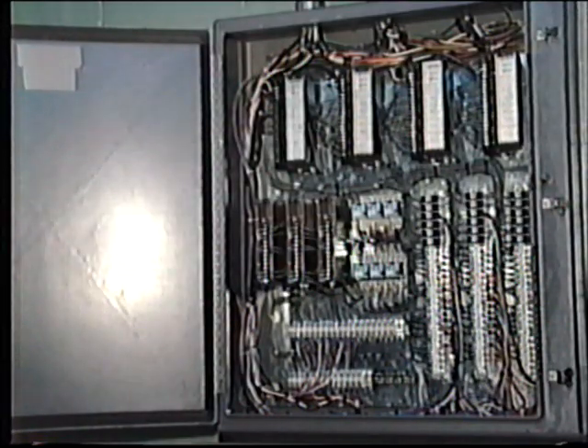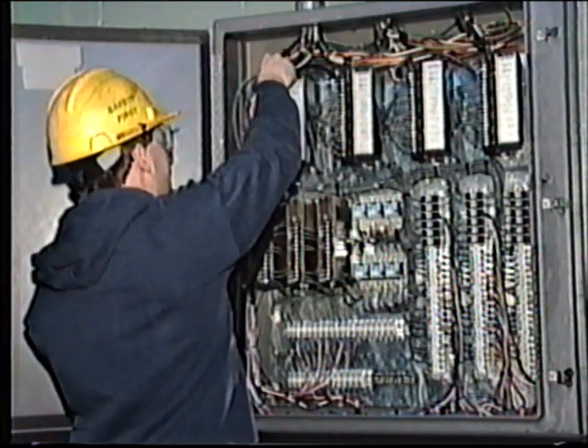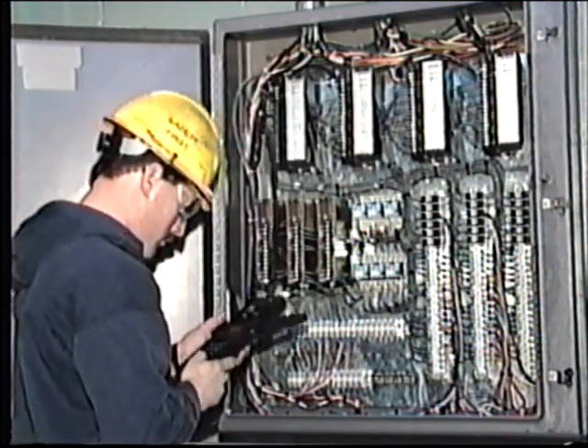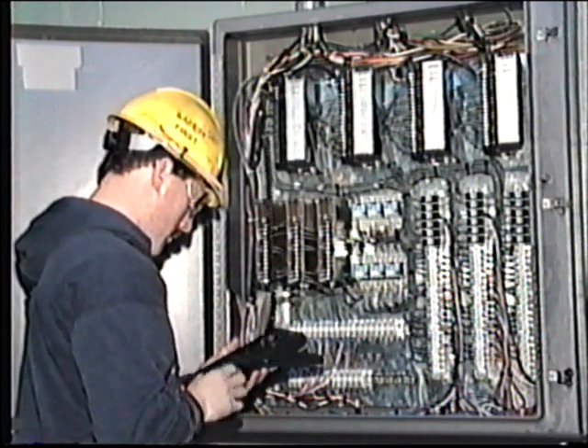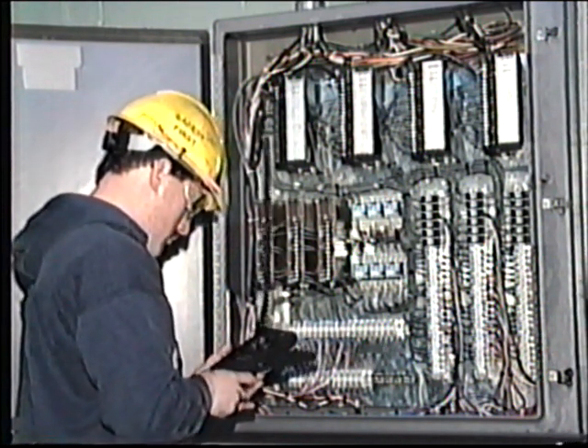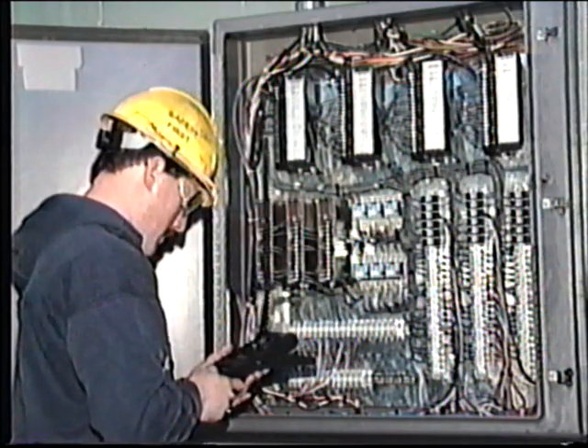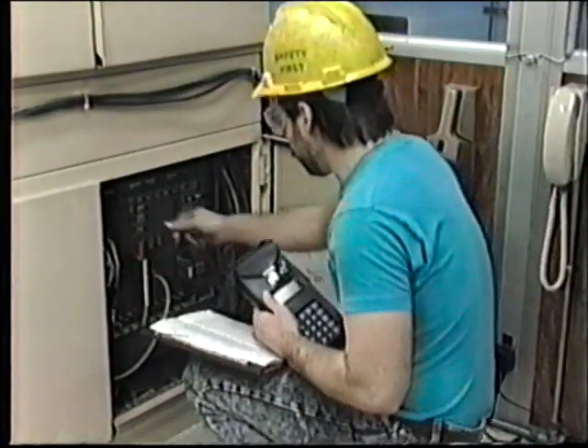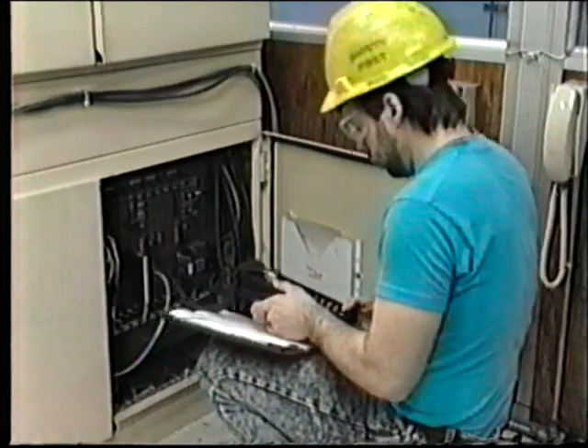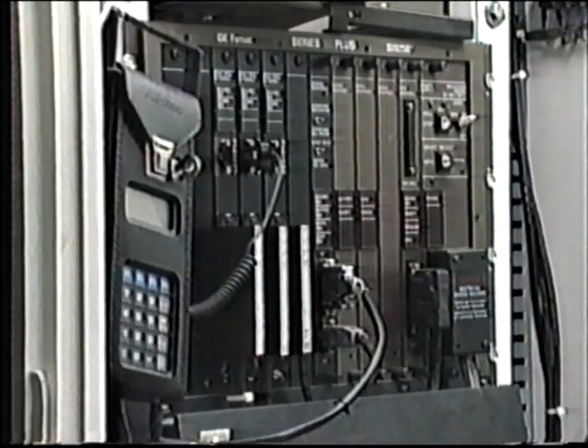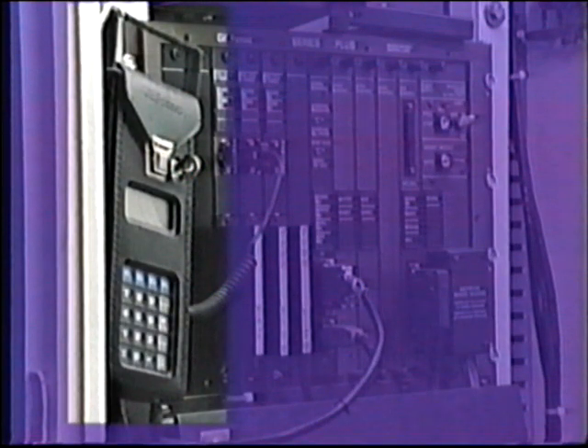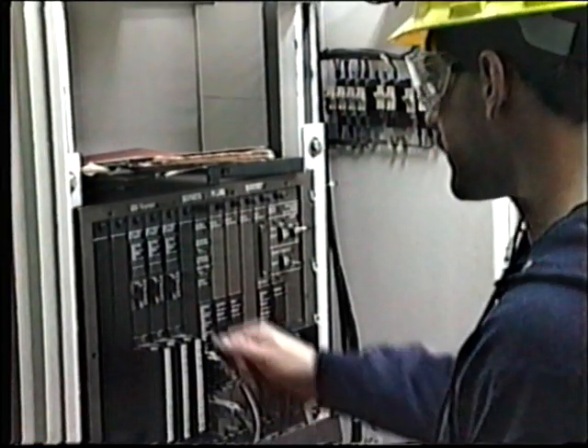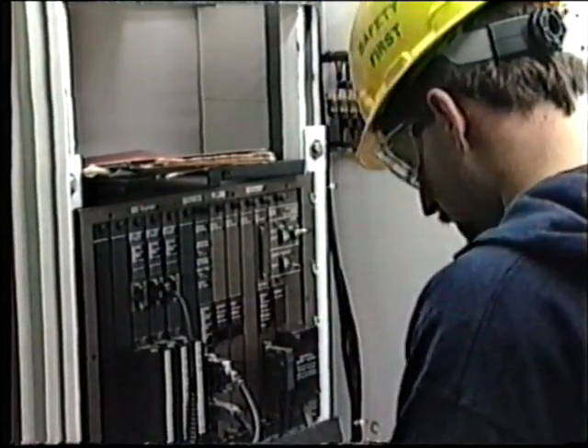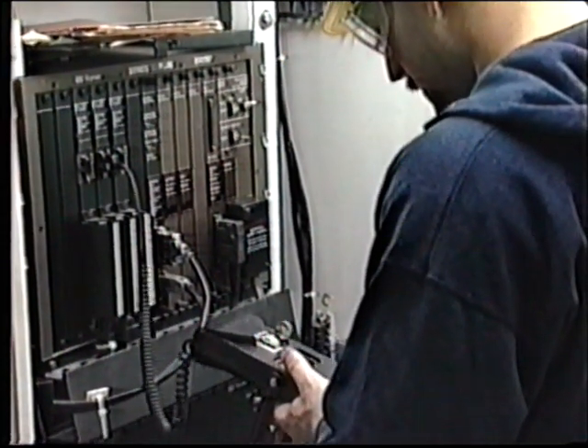A handheld monitor is provided to enable us to monitor the system and also to modify some of the parameters if required. This device can be plugged into the receptacle bus at the top of each I/O block. It may also be plugged into the bus controller located in the I/O rack. In some installations, the monitor is connected permanently into the bus controller so as to provide continuous monitoring. This handheld monitor is battery powered, so make sure that you keep it charged.